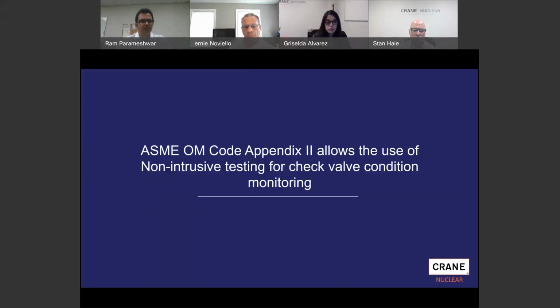As Ernie will expand from here, D&I has a place for you in the check valve program, but our message in this webinar is to lead with non-intrusive testing for valves that do not require D&I. Appendix 2 also allows the use of NIT as part of your condition monitoring program with the supporting trendable data that permits test interval frequency extensions for up to 16 years. We have slides later on that substantiate some of this.